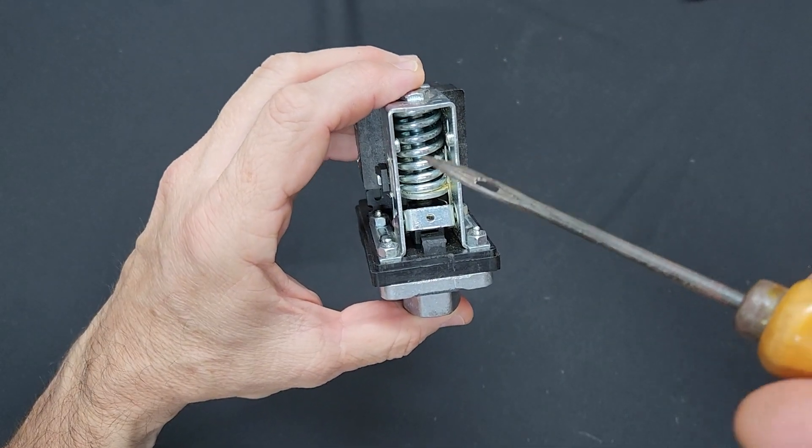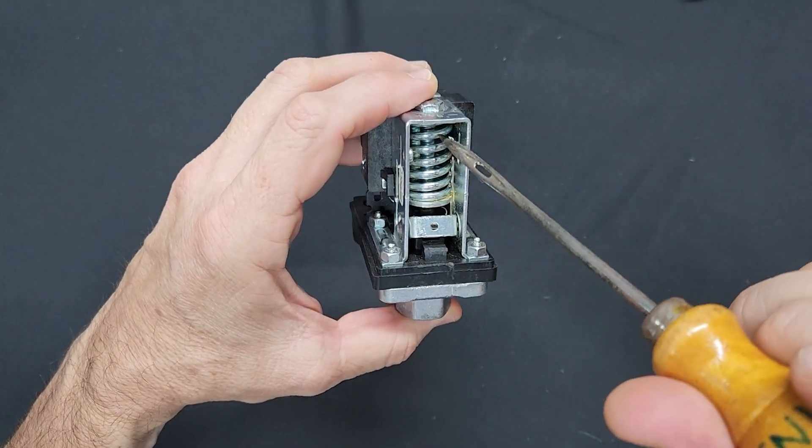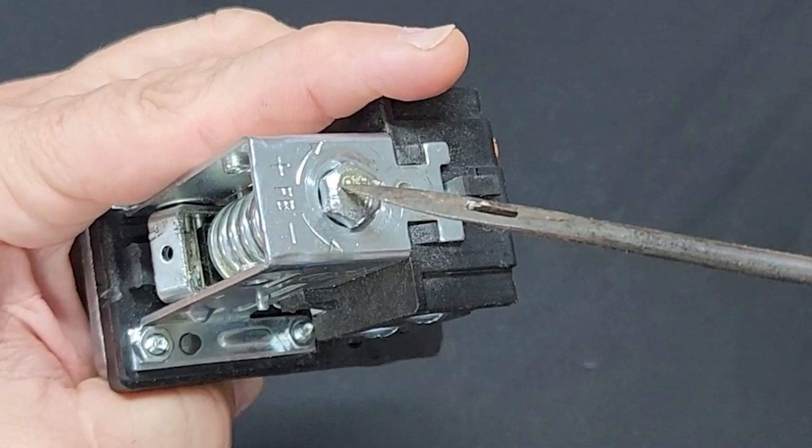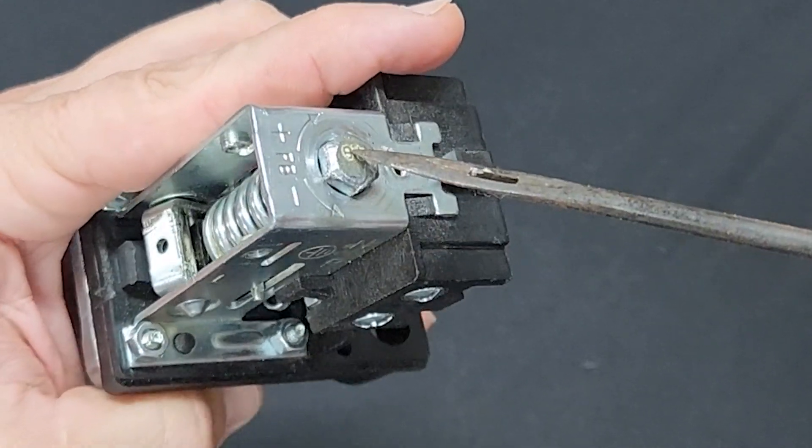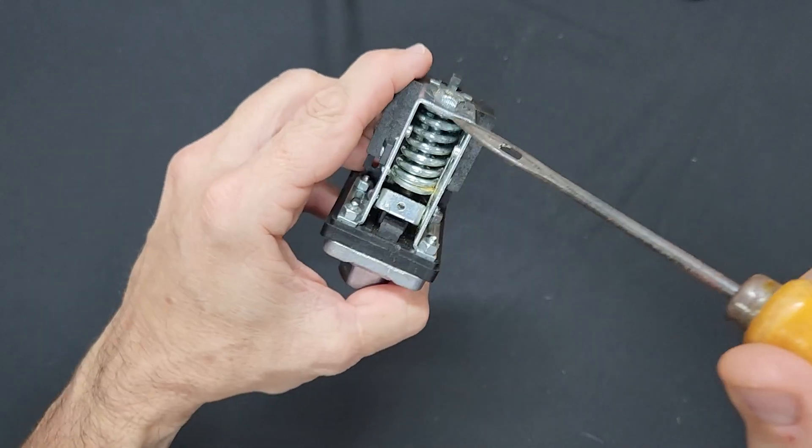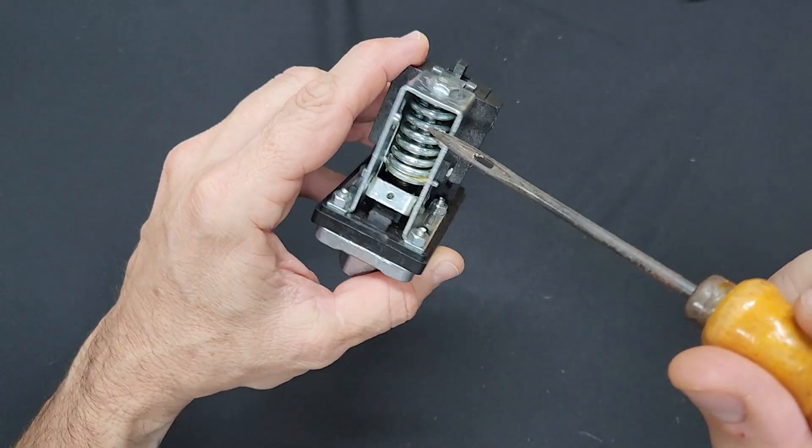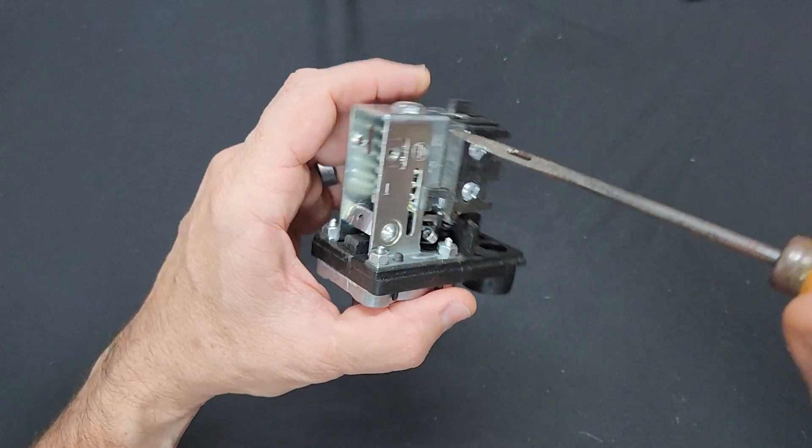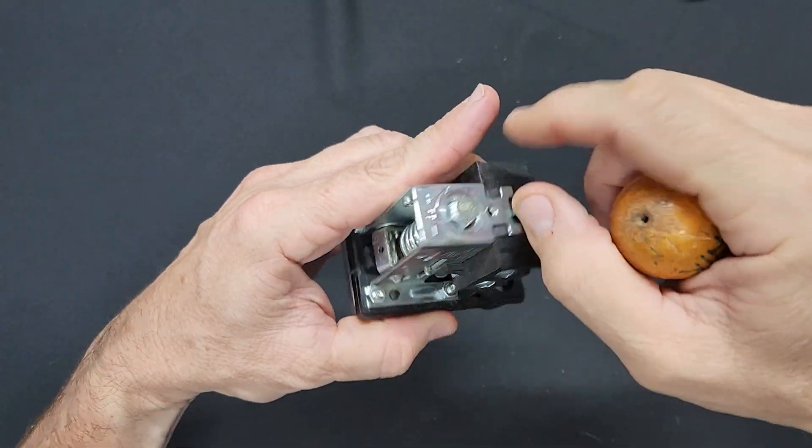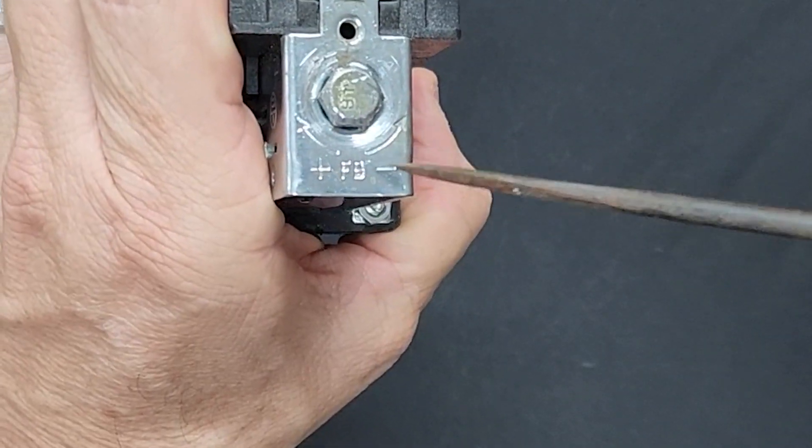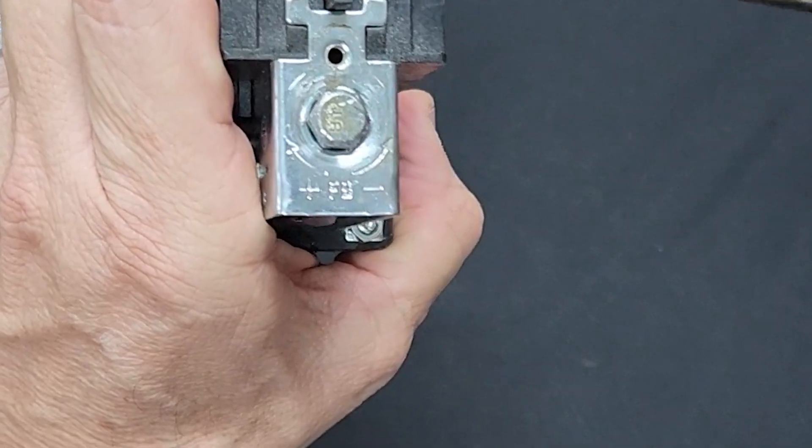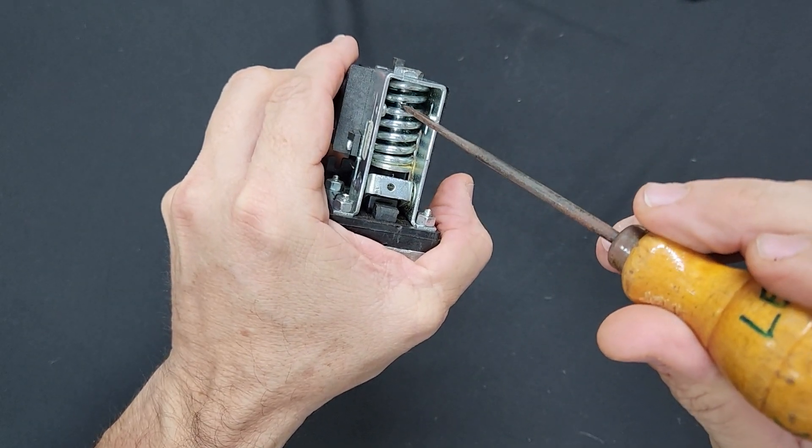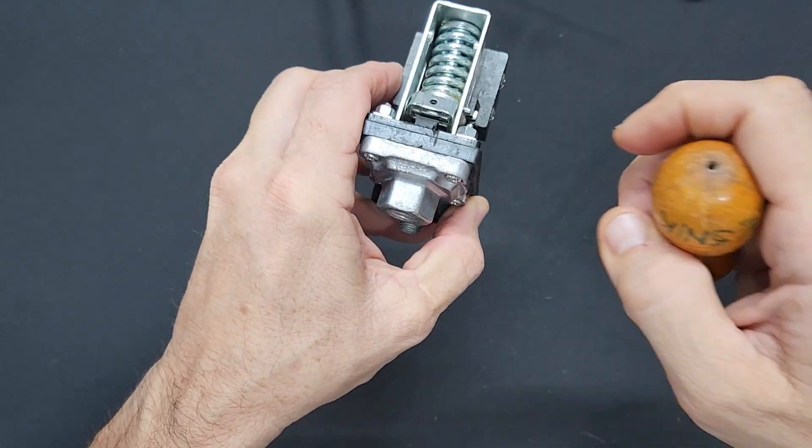I'll just show you first of all there is a spring here. This spring is very important and it's controlled by here. The tension of it can be loosened or increased, and basically what this does is this will control how much psi your tank is being pumped to.